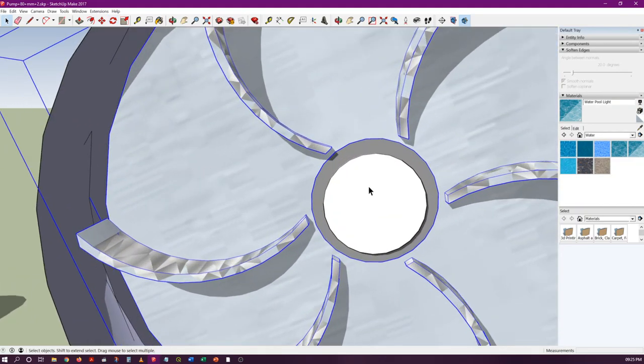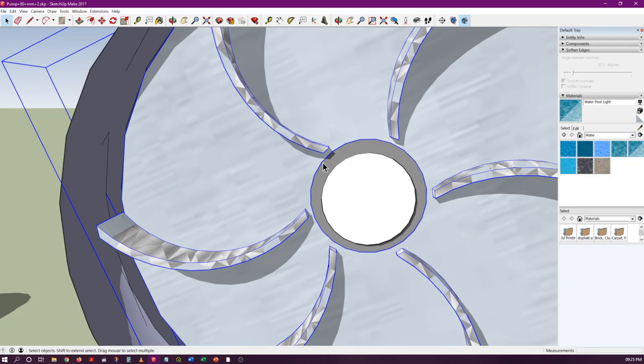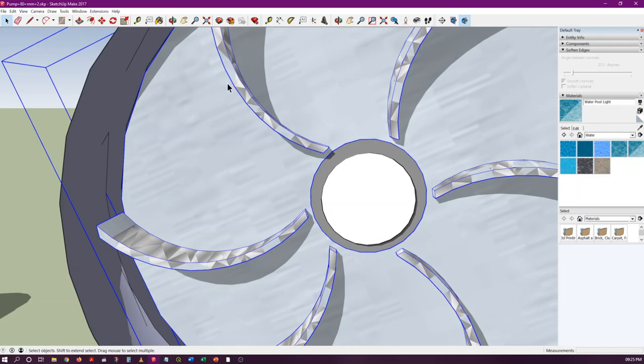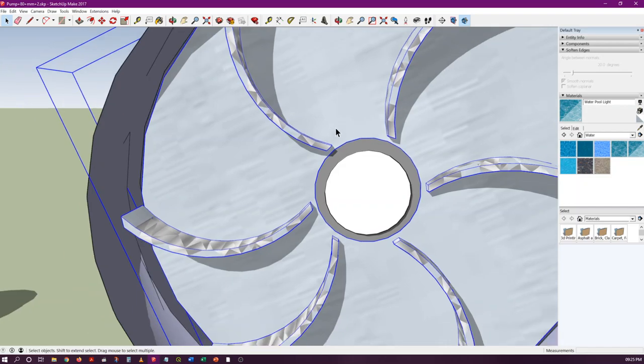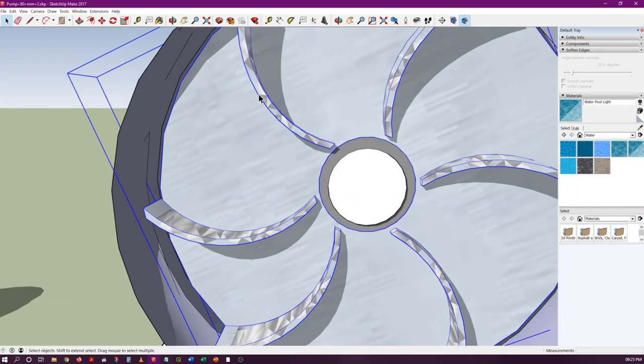Because these blades are moving in this direction, the water will be given velocity in this direction, which will have components both in the radial direction and the tangential direction. After it escapes the circumference of the impeller, it will move around this casing.